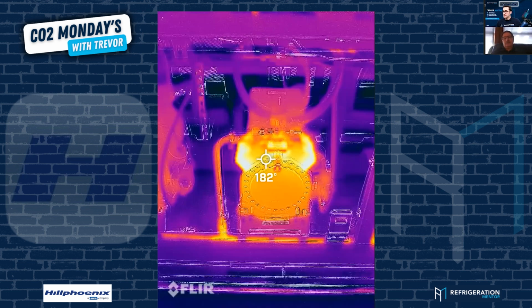Okay, from the light. Now, why would you take one of these shots, Paul? If you think you've got a discharge valve plate problem, take a thermal picture of this compressor. This is a good operating compressor. I took this because Trevor was looking for some pictures, so I took some nice thermal pictures for him to show him some operation. You can see the path. The compressor on the left isn't running. That's the number 2. This is the number 1, and you see the path of the gas from down to the bullhead to the right to the discharge separator.